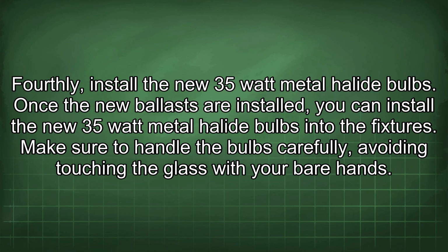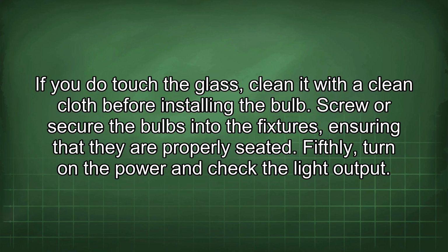Fourthly, install the new 35-watt metal halide bulbs. Once the new ballasts are installed, you can install the new 35-watt metal halide bulbs into the fixtures. Make sure to handle the bulbs carefully, avoiding touching the glass with your bare hands. If you do touch the glass, clean it with a clean cloth before installing the bulb. Screw or secure the bulbs into the fixtures, ensuring that they are properly seated.